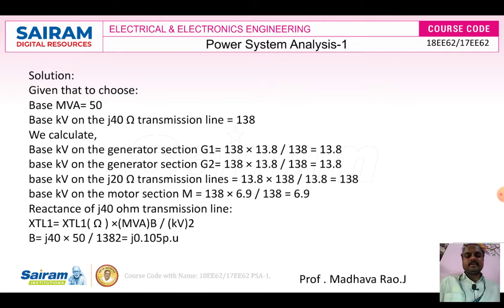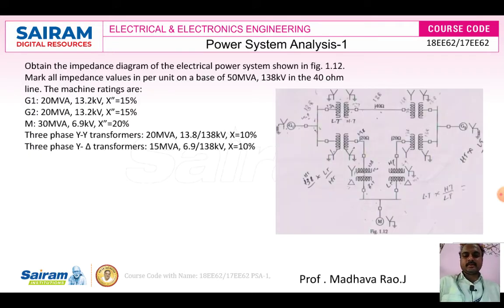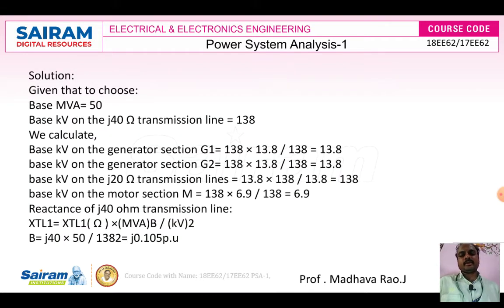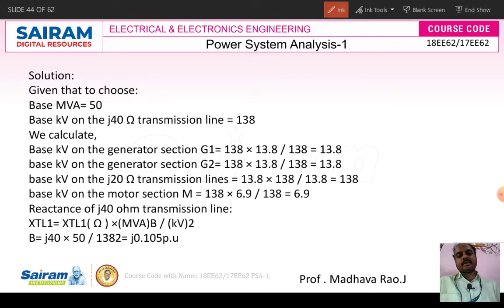For generator 1, the base kV on the high-voltage side is 138 kV. We have a 13.8 kV by 138 kV star-to-star transformer, so the base voltage on the low-voltage side is 138 × (13.8/138) = 13.8 kV. The base voltage of generator 2 is the same value.